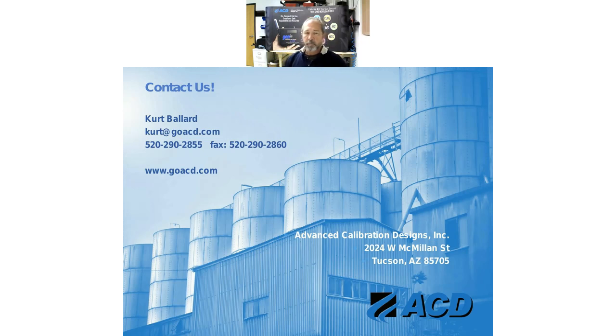Question from Dr. C. If we have only 1 or 2 instruments to calibrate, say every 3 months, then the cost of the ACD gas generator is high compared to calibration gas mixture. However, a typical QC lab in a refinery or petrochemical plant has a number of safety instruments to recalibrate every 3 months. Can you give us an idea of when the use of the ACD generator becomes cost effective? That's a good one. If you only need 1 concentration of cal gas, say you're going to calibrate at 25 ppm H2S, the MiniBump calibrator and generating source cost about as much as 2 or 3 cylinders. So if you're using fewer than 3 cylinders in a year for H2S, you're probably better off just buying cylinders.